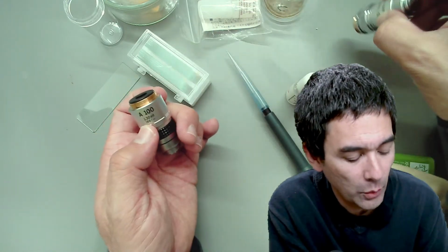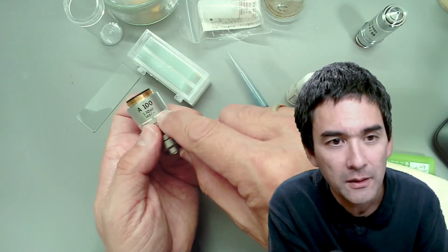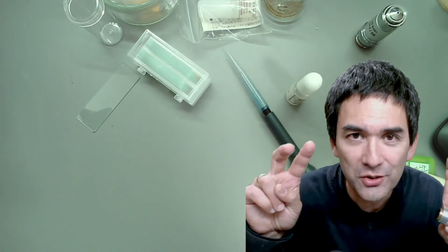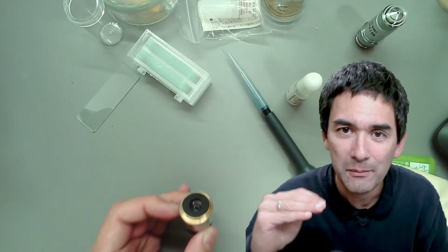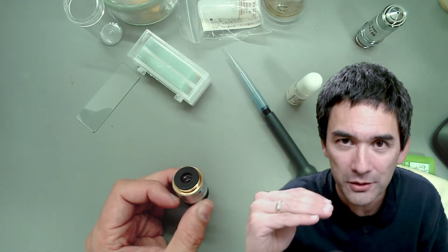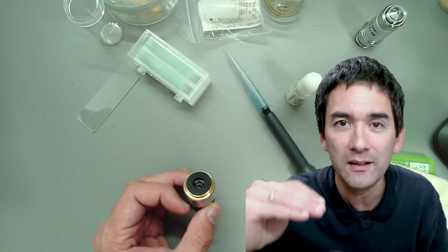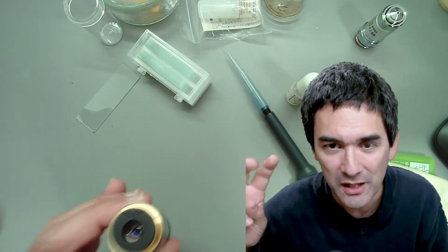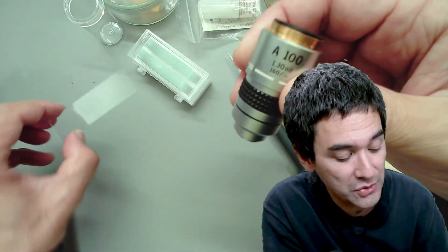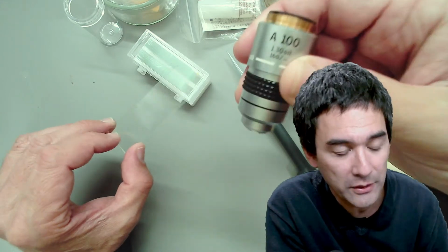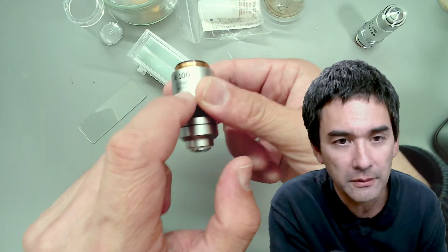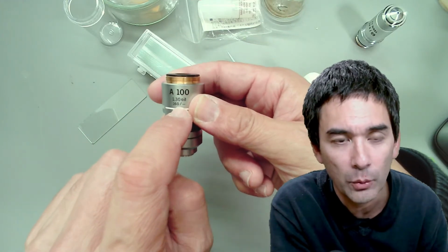Now over here in an oil immersion objective, you don't have that because the lens does not, under quotation marks, see a cover glass, because the light will be first in water, then in a cover glass, and then in the oil. So the lens actually does not see the cover glass, so to say. For this reason, and also because it's possible to use a slide without a cover glass for oil immersion, as I'm going to show you in a minute, there is no cover glass thickness written on many oil immersion objectives.